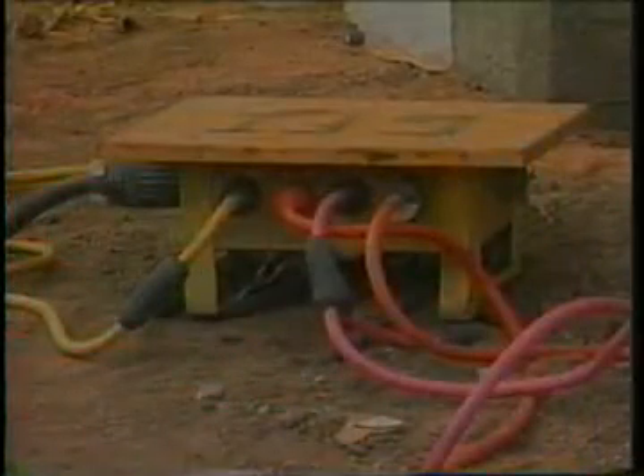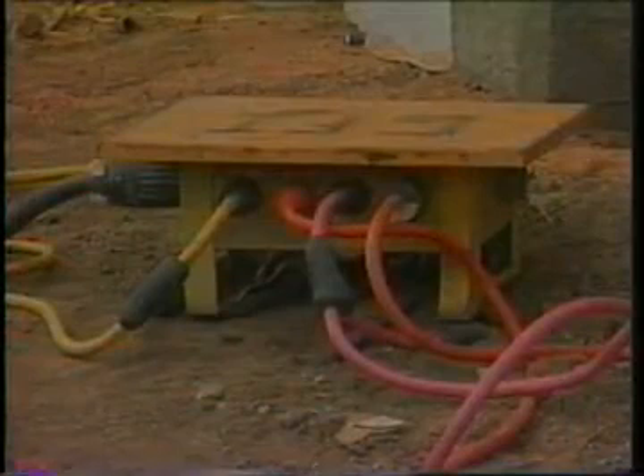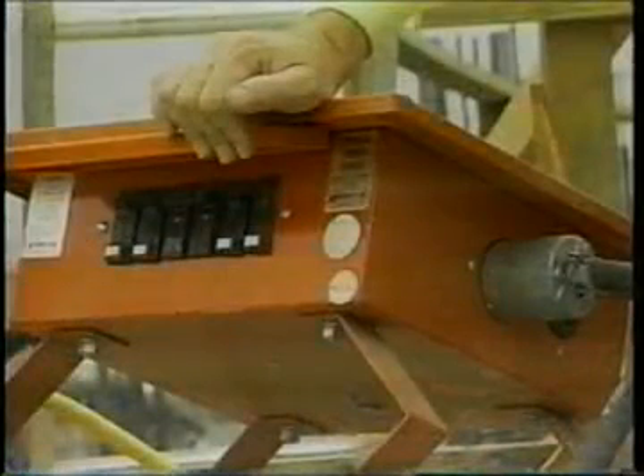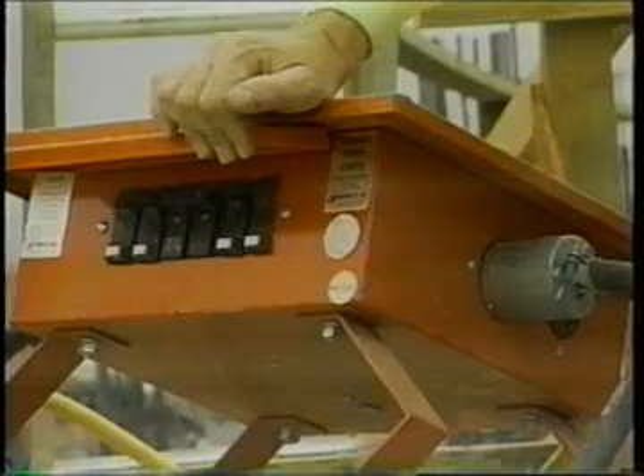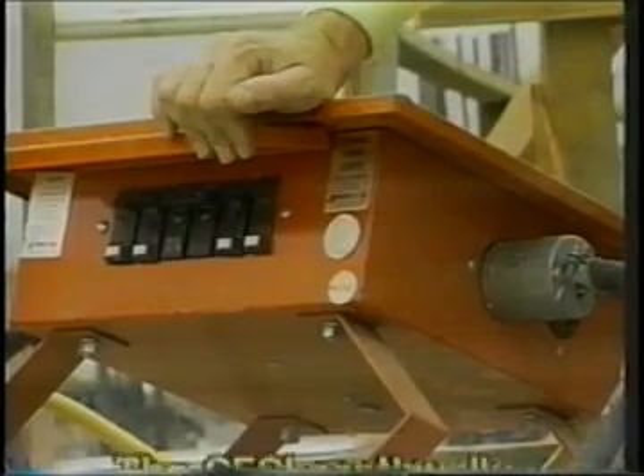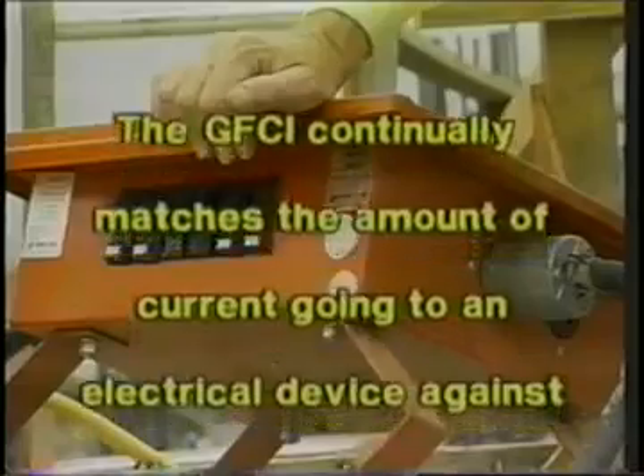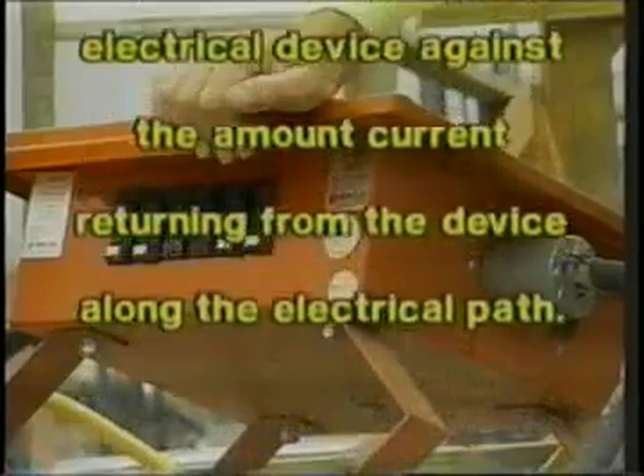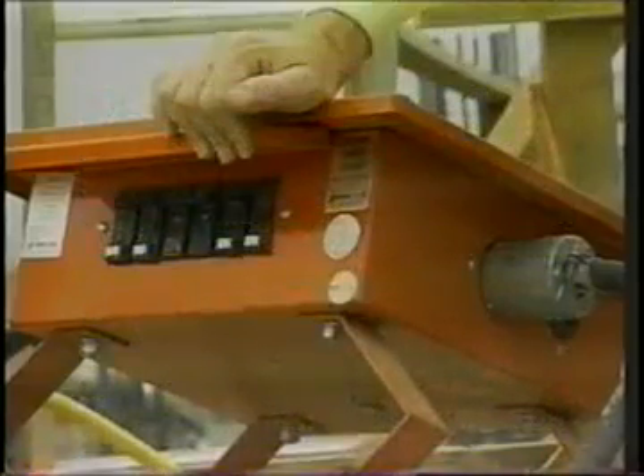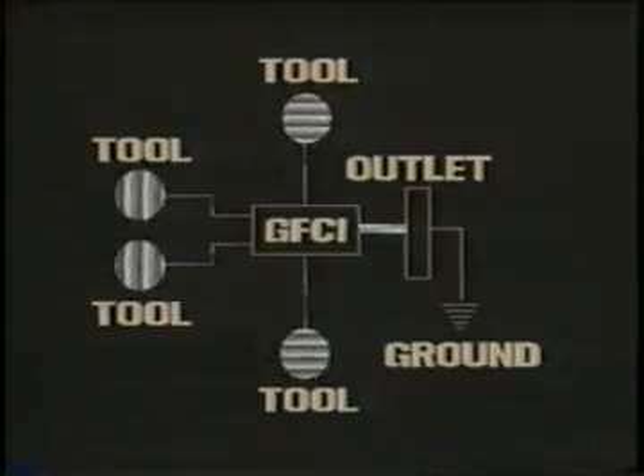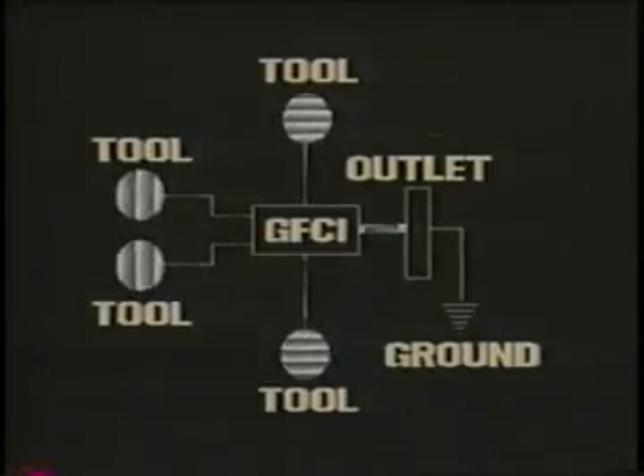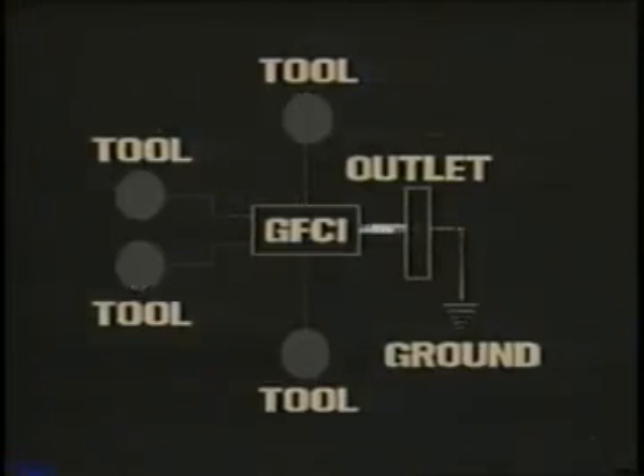The use of ground fault circuit interrupter, or GFCI, is one method used to overcome grounding and insulation deficiencies. The ground fault circuit interrupter is a fast-acting circuit breaker which senses small imbalances in the circuit caused by current leakage to ground and, in a fraction of a second, shuts off the electricity. The GFCI continually matches the amount of current going to an electrical device against the amount of current returning from the device along the electrical path. Whenever the amount going differs from the amount returning by approximately 5 milliamps, the GFCI interrupts the electric power within as little as 1/40th of a second.